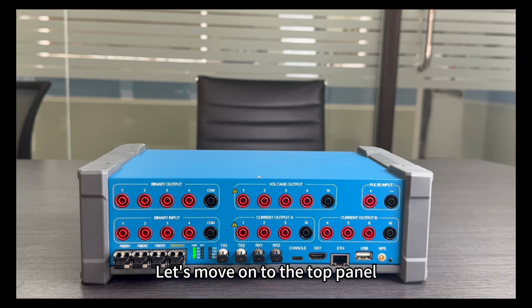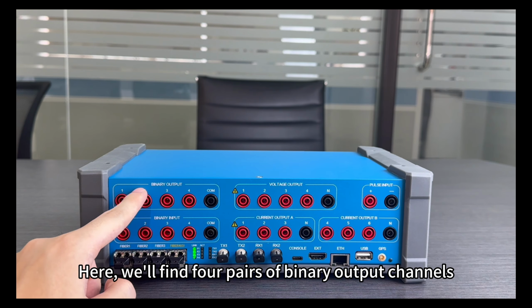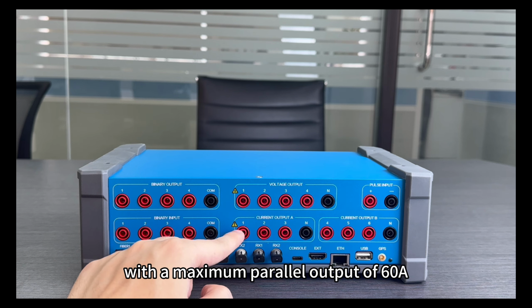Let's move on to the top panel. Here, we'll find 4 pairs of binary output channels, 4 pairs of binary input channels, and 4 voltage output channels, each supporting up to 300 volts. For current output, it offers 6 high-power channels, each rated for 20 amps, with a maximum parallel output of 60 amps when extra capacity is needed.